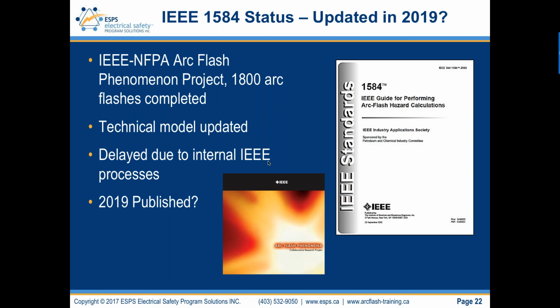In fact, I've encouraged clients to put a generic label on their equipment, and their generic label points back to the arc flash incident energy analysis studies and points back to their electrical safety program. Ultimately, a company's electrical safety program should control these studies being completed and these studies being reviewed. Again, the standards say every 5 years or more frequently.